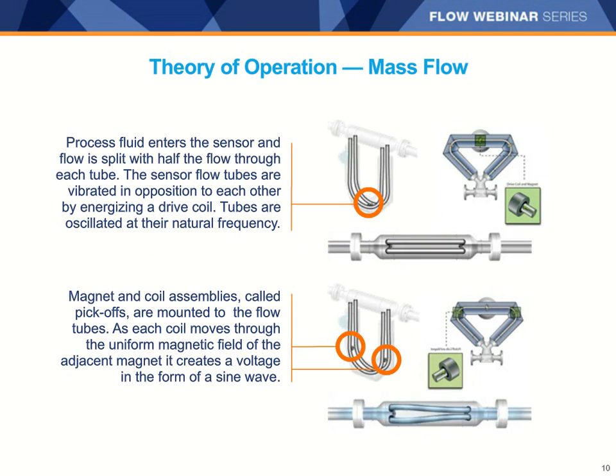All of our meters work in a similar way. The material to be measured enters the meter through the process connections and passes through a flow splitter that divides the material equally between the measurement tubes. 100% of the material passes through the measurement tubes. There's no slipstream inside the meter. The manifold and end connections of the meter provide a rigid structure to mount in your pipeline while isolating the measurement sections of the meter from any outside noise. The meter tubes are vibrated at their natural frequency with a low-voltage DC drive coil that you can see mounted to the tubes in the top center cutaway.